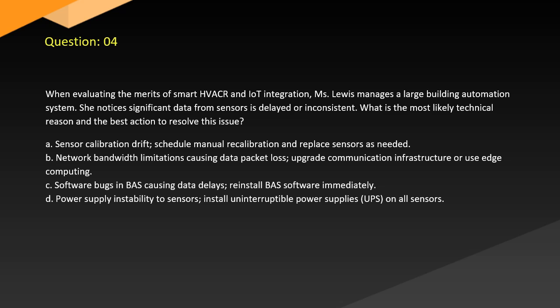A. Sensor calibration drift. Schedule manual recalibration and replace sensors as needed. B. Network bandwidth limitations causing data packet loss. Upgrade communication infrastructure or use edge computing. C. Software bugs in the BAS causing data delays. Reinstall BAS software immediately. D. Power supply instability to sensors. Install uninterruptible power supplies (UPS) on all sensors.